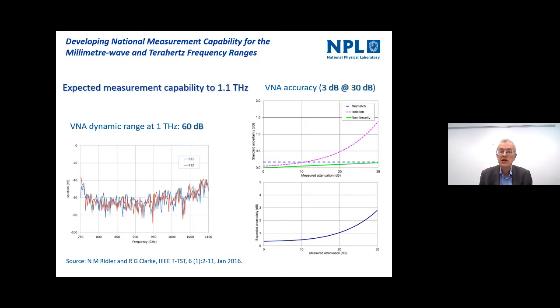When we run the computations on waveguide misalignment and aperture, etc., as I've just described, then we can predict the overall accuracy of the network analyzer. And typically, if we're measuring, say, an attenuation of about 30 dBs, then we would expect an accuracy of about 3 dB in that 30 dB. So about 10%, which doesn't sound very good as far as a measurement goes. So normally with a network analyzer, we would have much more accurate measurements than that.